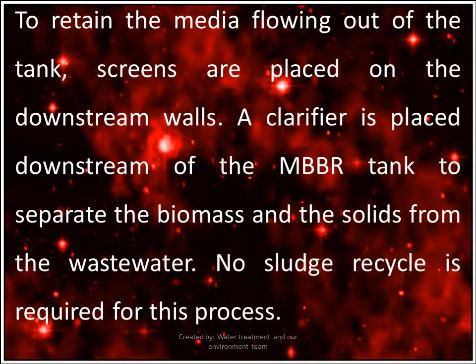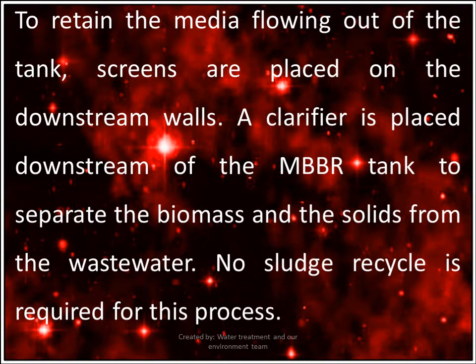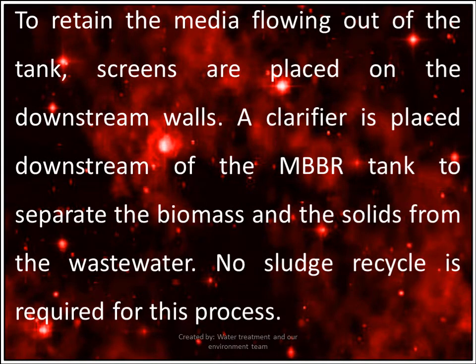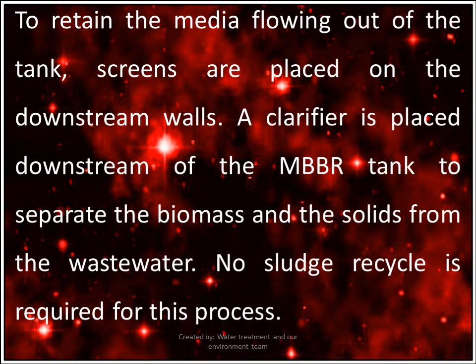To retain the media and prevent it from flowing out of the tank, screens are placed on the downstream wall. A clarifier is placed downstream of the MBBR tank to separate the biomass and solids from the wastewater. No sludge recycle is required for this process.